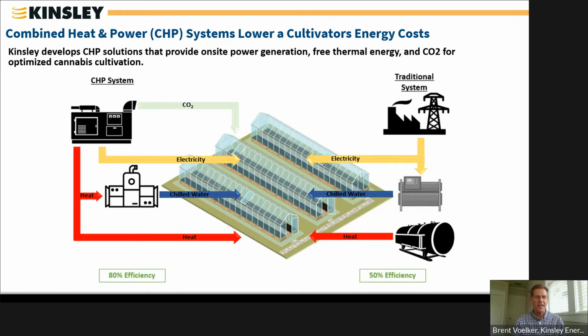On the left-hand side, we've got a combined heat and power system that does all of those functions from a single source. This is the whole point of combined heat and power, is to locate electric power generation on site at the point of use where the waste heat from the generator can be captured and put to use in the facility. So here we use it in two ways. We also provide the heat directly in the form of hot water, just as a boiler would do for reheating. And then any excess thermal demand we put through a device called an absorption chiller, which makes chilled water.